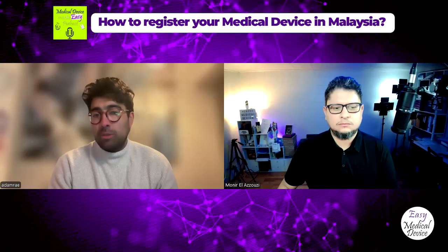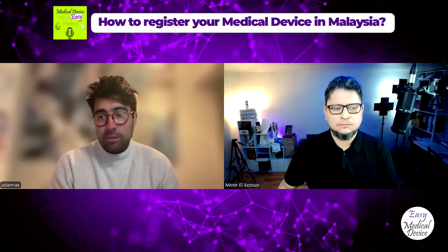And the Malaysian Medical Device Act of 2012, Act 737, is enforced by the Medical Device Authority. It requires ISO 13485 for manufacturers. You require an authorized rep, an importer, and a distributor. So the post-market surveillance and technical documentation, if you're doing it elsewhere, you can do it in Malaysia, basically. You're not going over and above what's in place elsewhere, essentially.